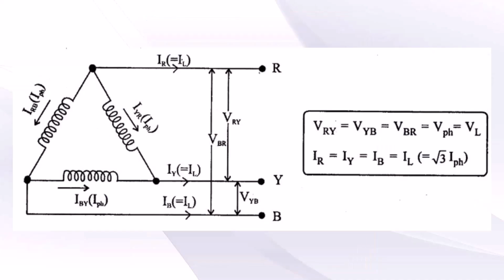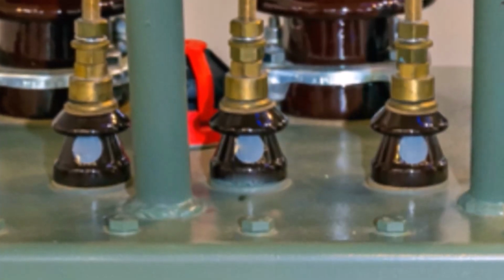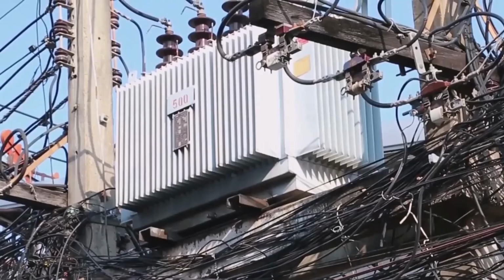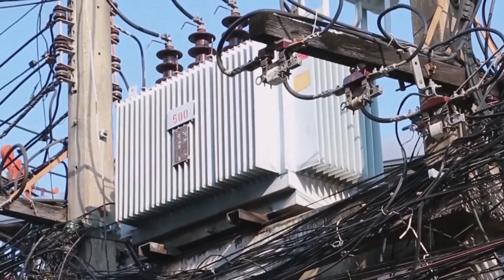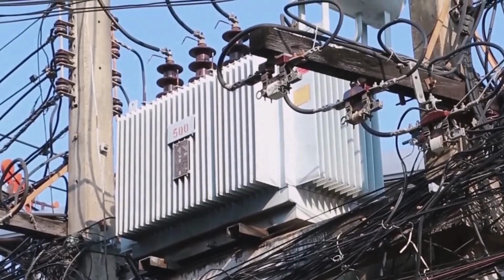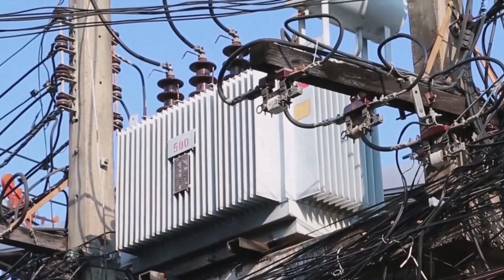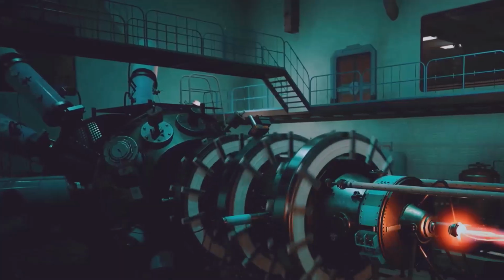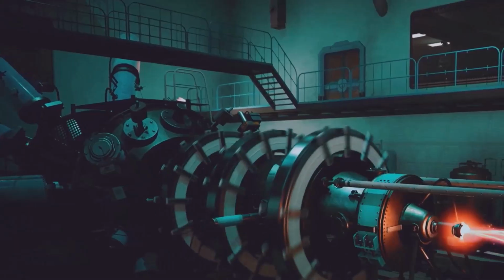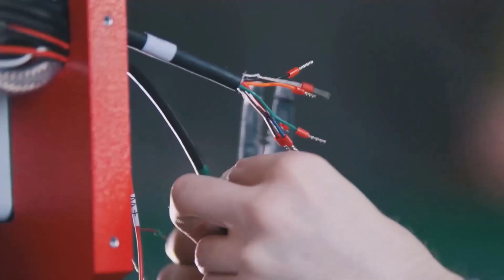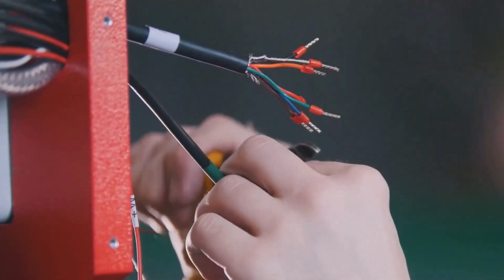Every system has its strengths and weaknesses, and the delta connection is no exception. Let's start with the good stuff. One of its biggest advantages is its reliability. Since the phases are connected in a closed loop, if one of the three-phase windings in a delta transformer fails, the other two can still deliver three-phase power. It won't be at full capacity, of course, but it can keep things running in an emergency. This is known as an open delta or V connection.